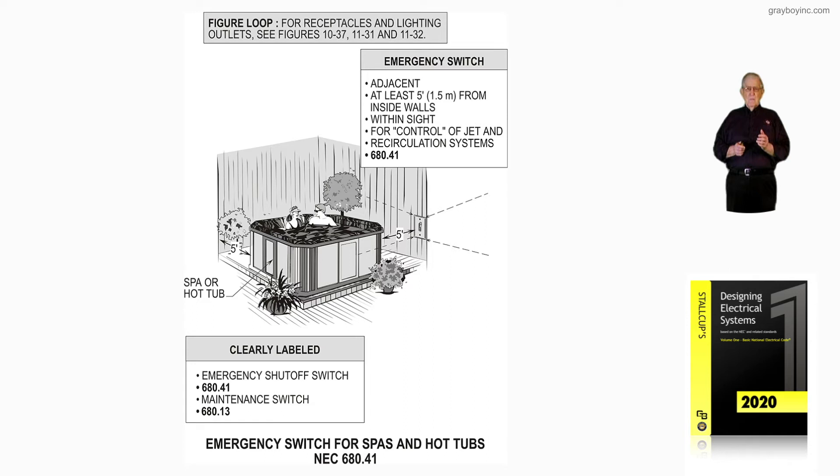Notice, clearly labeled in the boxed-in information, the emergency cutoff switch can be found with its requirements in 680.41. You also have a maintenance switch, which is in accordance with 680.13. So there are two types of switches involved here.